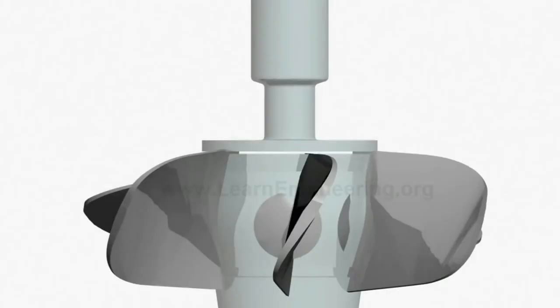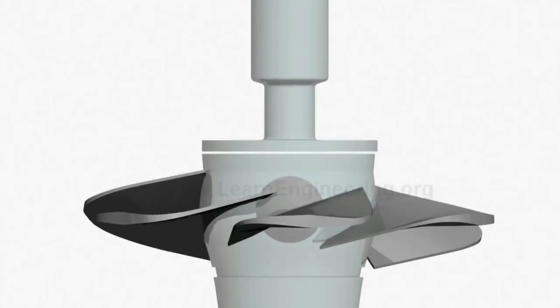These blades are adjustable. When the flow rate is high, the blade pitched vertically or parallel to the axis and the relative velocity of the flow is more axial. When the flow rate is low, the blade pitched tangentially and hence the relative velocity of the flow is more tangential. But in all cases of flow variation and blade pitching, the optimum angle of attack will remain the same.